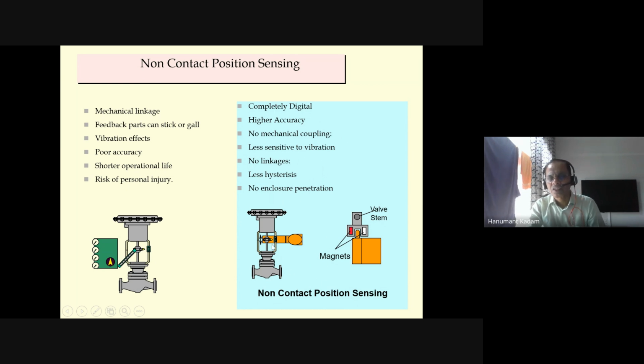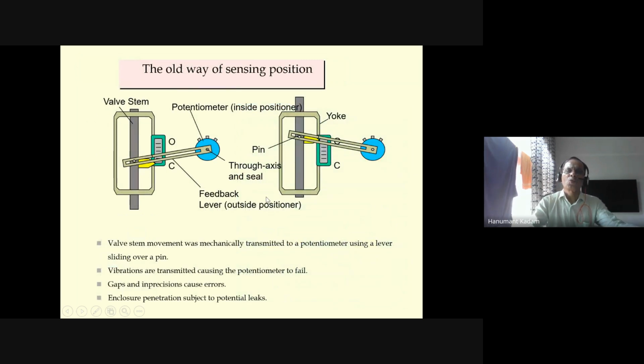So you can see here magnets are there. This is a valve stem, and you can see magnets here. So this way the accessory is there. This is non-contact. So the old way of sensing positioners, old way, valve stem. This is a feedback lever outside the positioner. And there is a scale on the valve here, which shows valve open, valve close, and this potentiometer through an axis inside the positioner, like this.